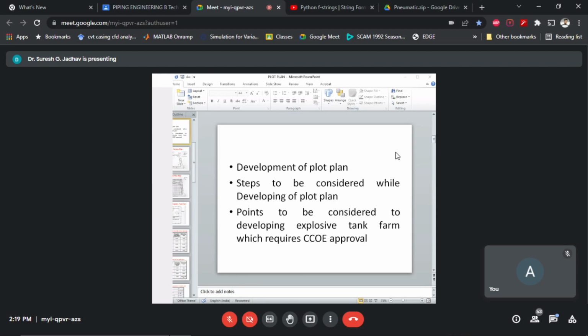In case of excluded petroleum, the capacity of the dike enclosure could be based on spill containment and not containment on the tank ruptures.